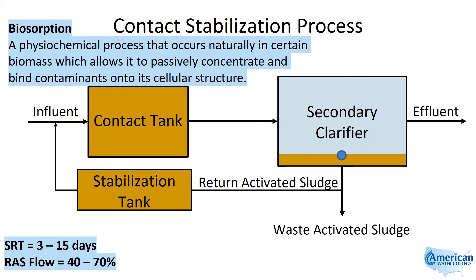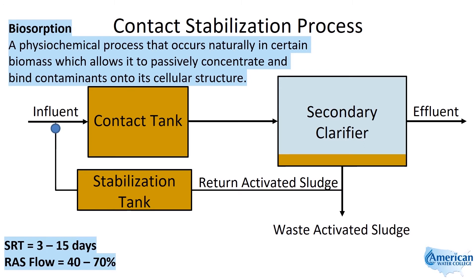The microbes are then settled and sent to the stabilization tank, where the organic matter that's been taken up in the contact tank is then stabilized while undergoing aerated conditions for a few hours. The microbes remain there for several hours so that the waste can be stabilized.